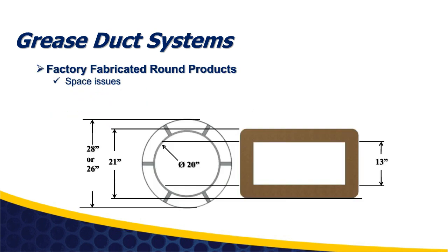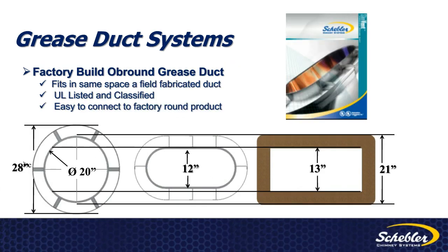One struggle we all have with UL-listed fabricated products is most overhead space designed for ductwork ends up being rectangular, whether it be air ducts or whatever. And now factory-built products for grease duct are coming out of factories round. So in essence, we're trying to put the round peg in the square hole. So one thing Schebler's done is obtained and developed a product that has a UL listing classification that is obround, which we term as slim vent, to allow us to fit in the same space as rectangular ductwork. And in conjunction with our round product, it allows us to do a complete UL listed and classified system that doesn't require any field welding and that has all the grease duct fire safety that you have in the UL listed product.